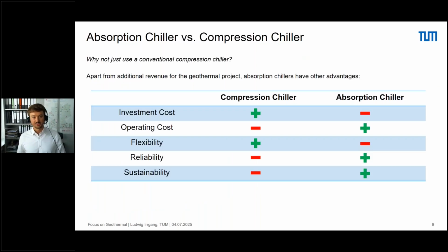Apart from geothermal heat use, absorption chillers have other advantages compared to compression chillers. The main disadvantages are higher investment costs, and in high load fluctuation they might be less flexible. On the other hand, operating costs can be reduced a lot with cheap heat available, and absorption chillers are usually quite reliable since there are no compressors or moving parts like a compression chiller. Regarding working fluids, absorption chillers have better sustainability since they have no global warming potential, ozone depletion potential, and are not affected by PFAS regulations.